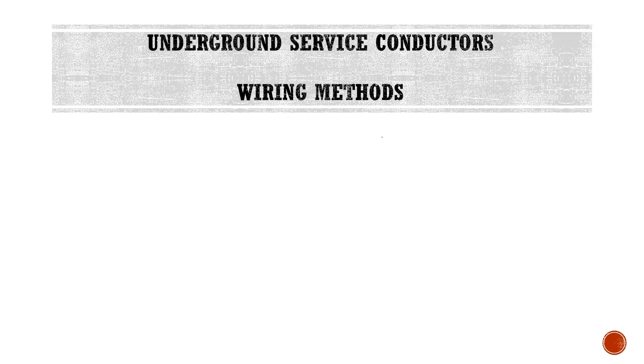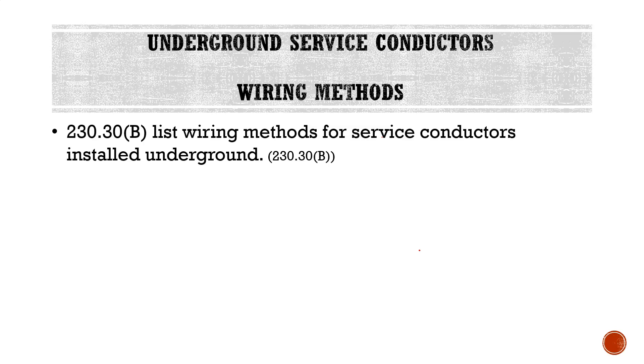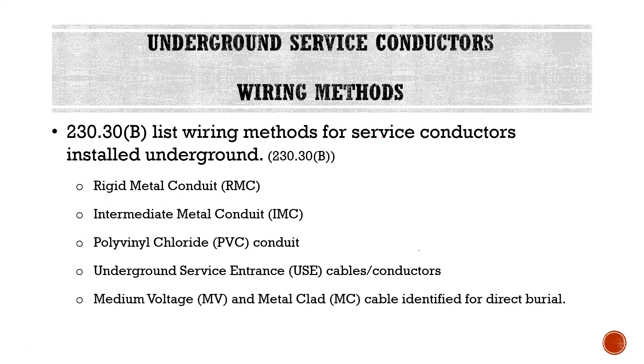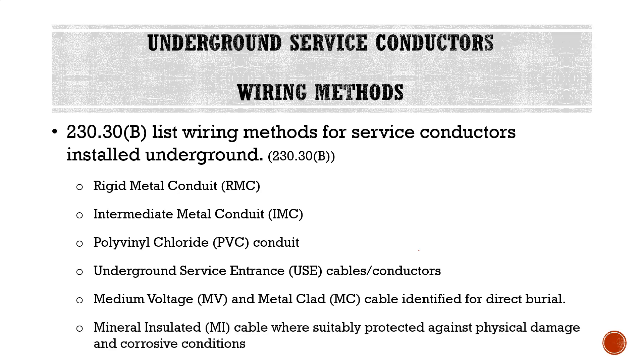Now we're going to look at some specific wiring methods. Section 230.30B lists wiring methods for service conductors installed underground. Where installed underground, the permitted wiring methods are: rigid metal conduit, intermediate metal conduit, PVC, underground service entrance (USE) cables and conductors, medium voltage and metal clad cable identified for direct burial, and mineral insulated cable where suitably protected against physical damage and corrosive conditions. Requirements for mineral insulated cable will be based on the environment they're installed in, as some areas are subject to more damage than others.